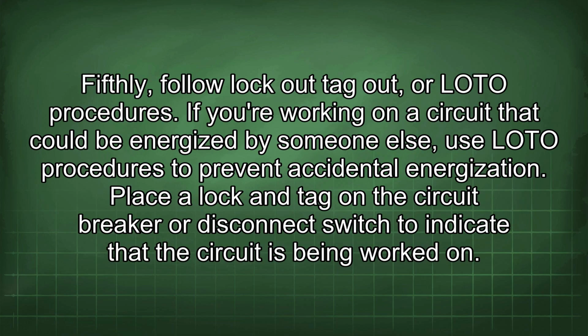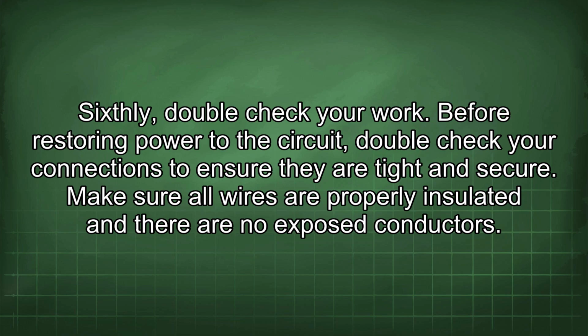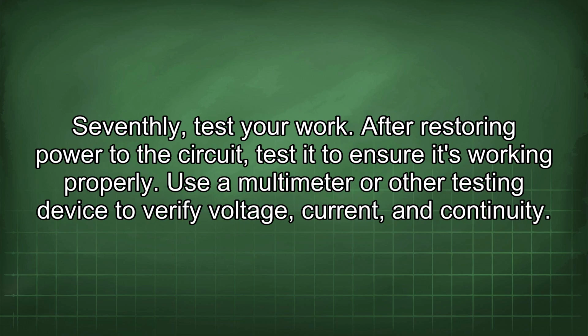Fifthly, follow lockout, tagout procedures. If you're working on a circuit that could be energized by someone else, use lockout procedures to prevent accidental energization. Place a lock and tag on the circuit breaker or disconnect switch to indicate that the circuit is being worked on. Sixthly, double-check your work. Before restoring power to the circuit, double-check your connections to ensure they are tight and secure. Make sure all wires are properly insulated and there are no exposed conductors. Seventhly, test your work. After restoring power to the circuit, test it to ensure it's working properly. Use a multimeter or other testing device to verify voltage, current, and continuity.